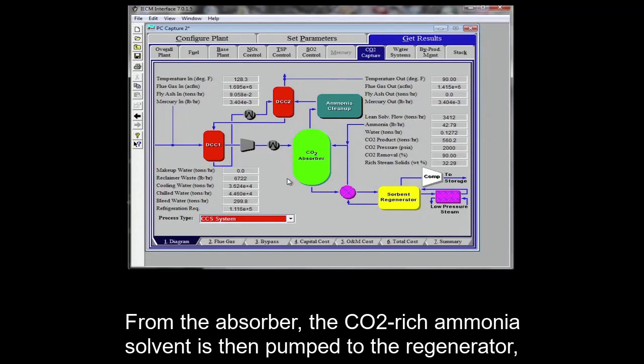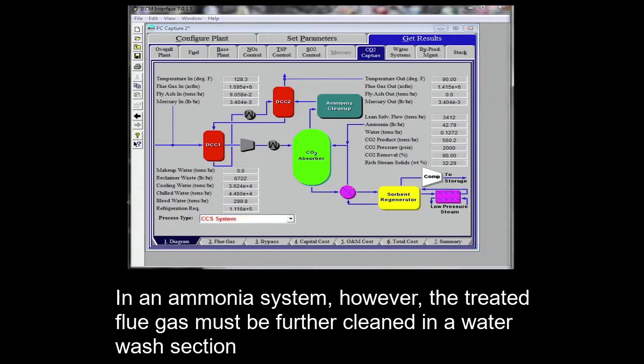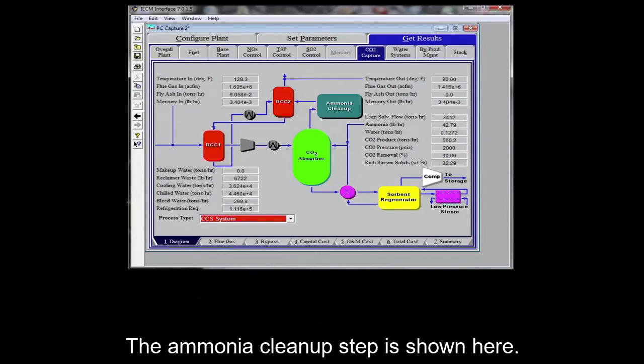Because of the low absorber temperature, typically around 10 degrees Celsius, this process is often referred to as a chilled ammonia process. From the absorber, the CO2 rich ammonia solvent is then pumped to the regenerator where the CO2 is released via heat with steam just as the amine system. In an ammonia system, however, the treated flue gas must be further cleaned in a water wash section to prevent high levels of vaporized ammonia from being released into the atmosphere from the power plant stack. The ammonia cleanup step is shown here.